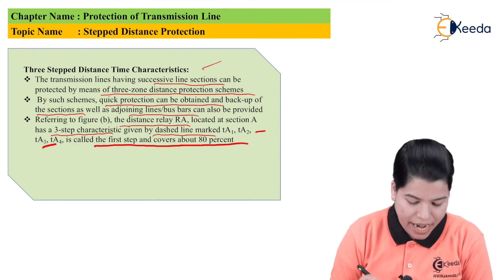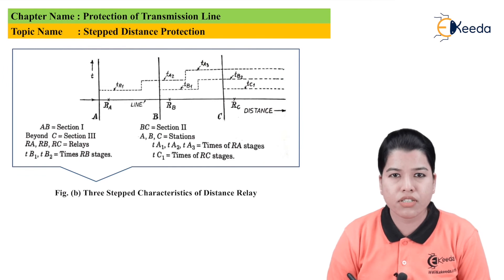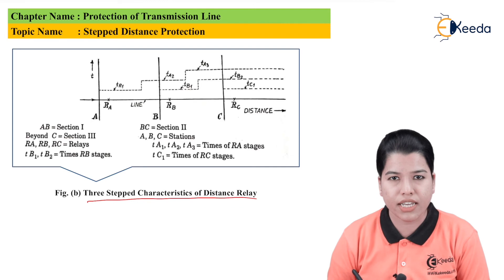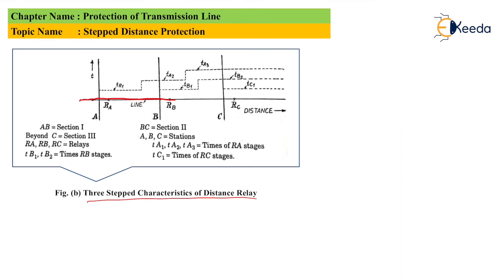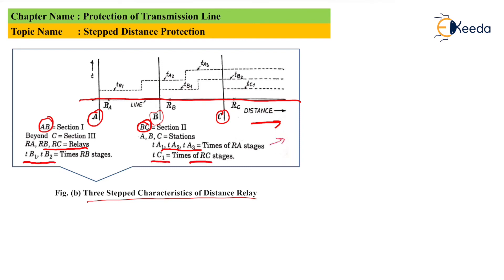The first step covers about 80% of the line section. The figure shows the diagram for the three-step characteristic of the distance relay. The complete line is divided into three sections A, B, and C, where AB is the first section, BC is the second section, and the section beyond point C is the third section. RA, RB, and RC are the relays at each station. TA1, TA2, TA3 are the operating times of the RA stages, TB1 and TB2 are the times of RB stages, and TC1 is the time of the RC stage.